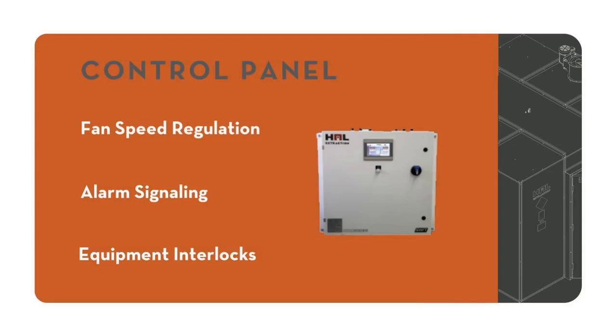And again, that sensor will also send a signal to the control panel, and that's going to turn the light alarm on as well. And then if you reach 25%, then that sensor is still going to be sending a signal, but that sound alarm is going to go off as well. The great thing about this fan speed is you're not dumping a bunch of preconditioned air out into the environment all the time. So you're at that base airflow rate. You're saving energy and power by just running at the base airflow rate and only ramping up that airspeed when you have that hazardous environment created.